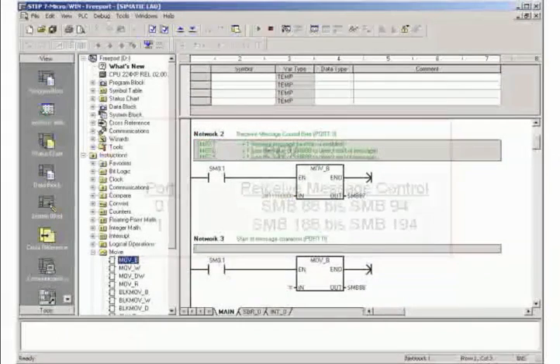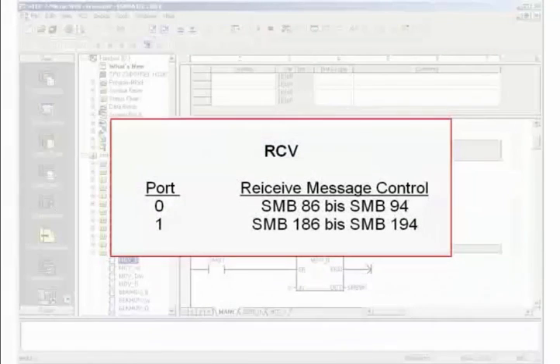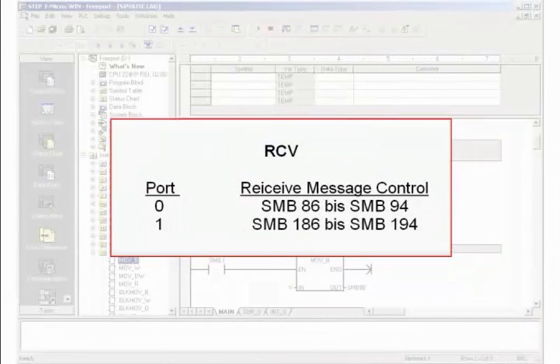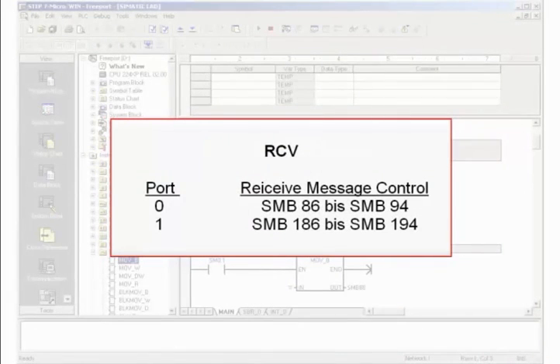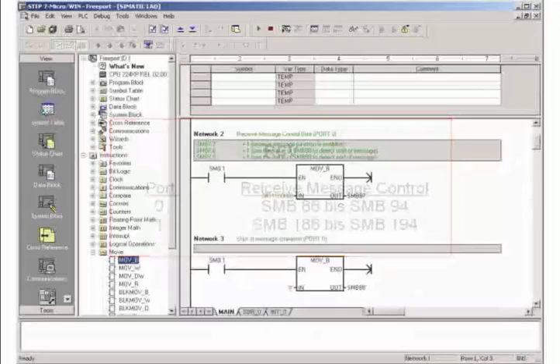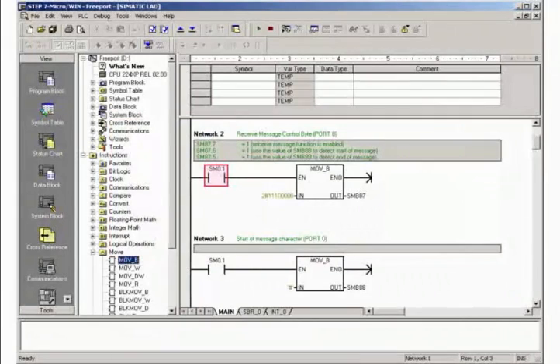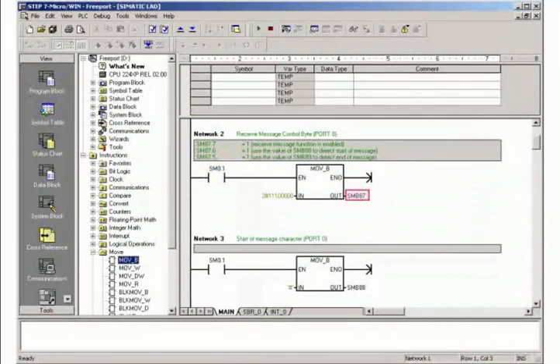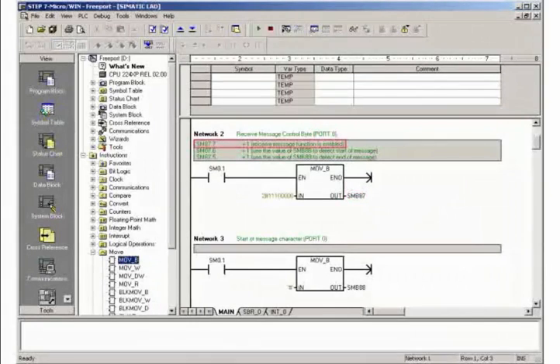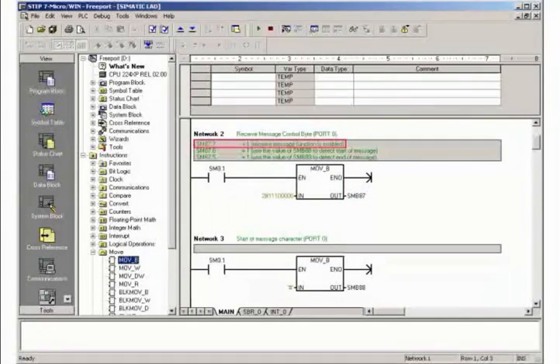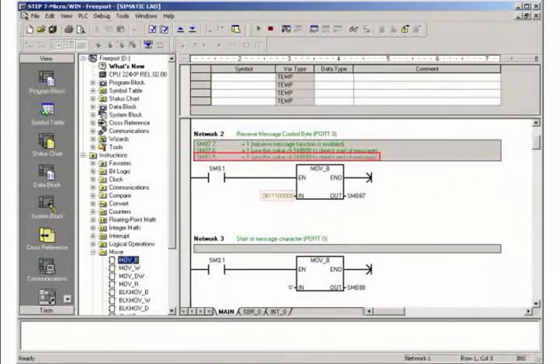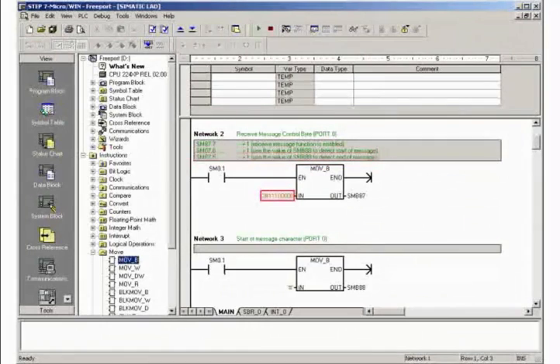The special memory byte area 86 to 94 or 186 to 194 must be initialized depending on the used communication port to control the RCV function. In Network 2 you initialize the control byte SMB87 for receiving messages via port 0. Enable the message function and activate the detection of start and end characters of the message.